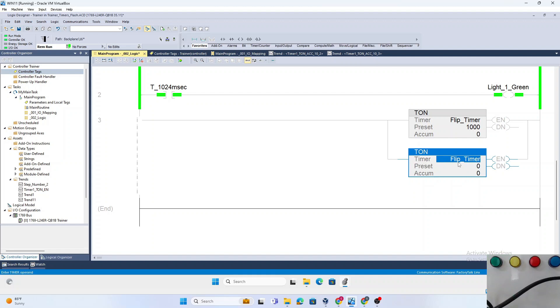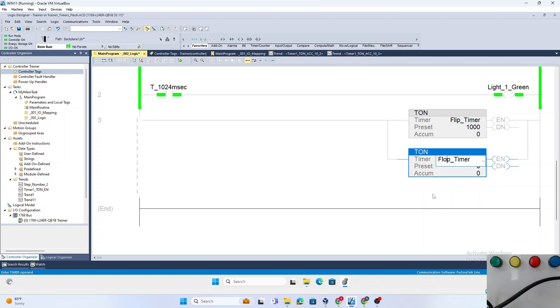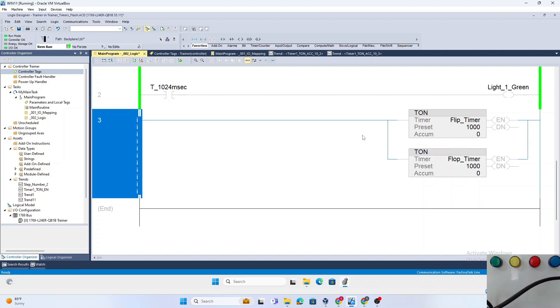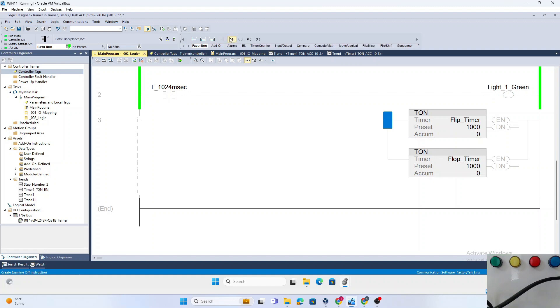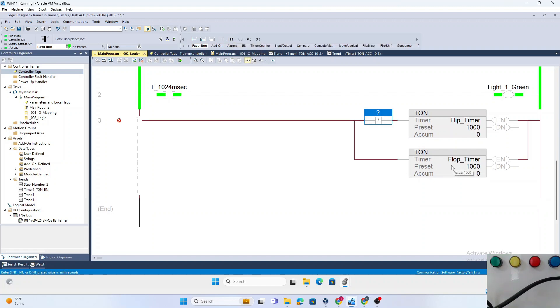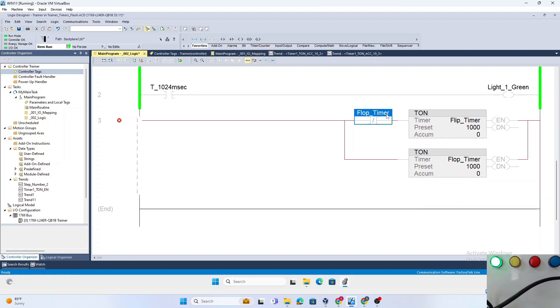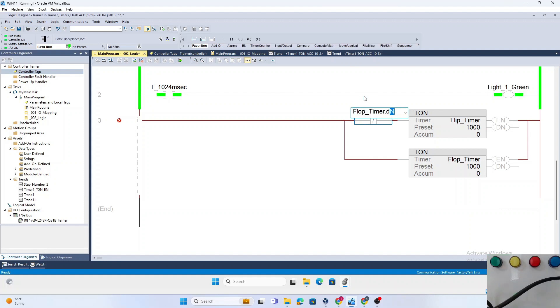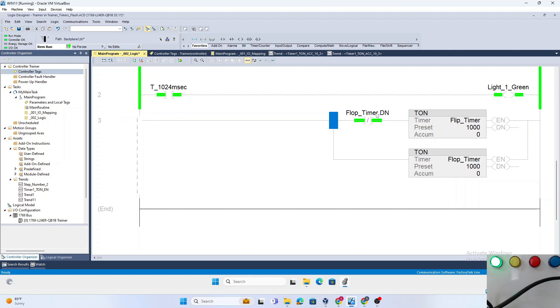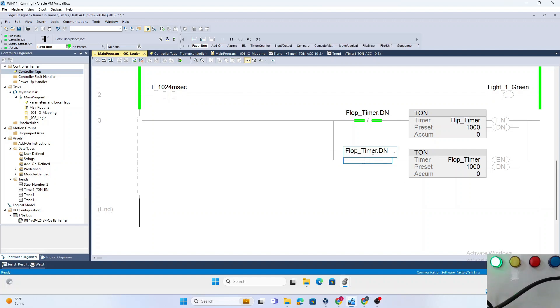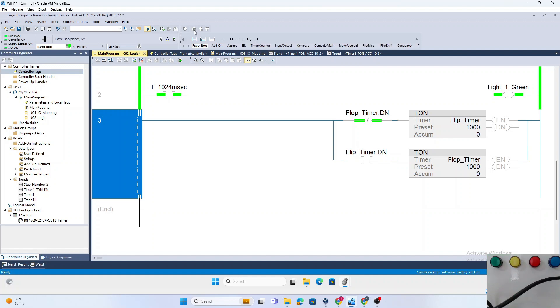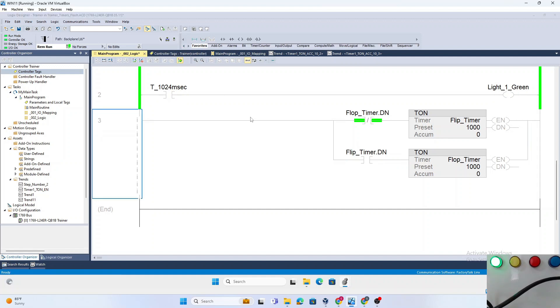And we'll go ahead and do a Flop_Timer. Create new, create new. We'll make that one also 1000 milliseconds. We will make this self-timing by using Flop_Timer NOT done to start the Flip_Timer, and we will use the Flip_Timer done to start the Flop_Timer. Go ahead and assemble it.